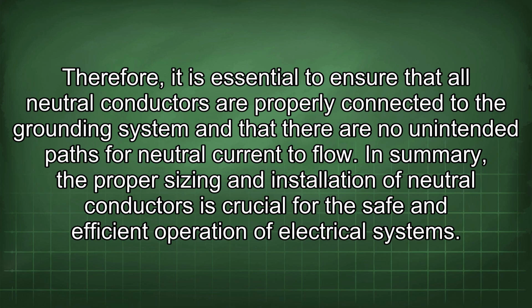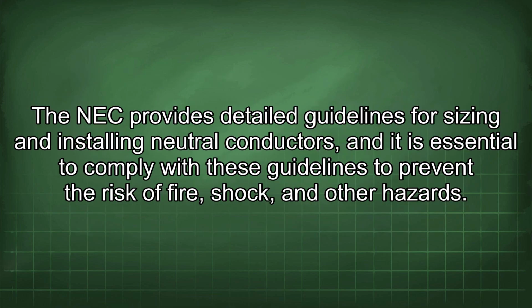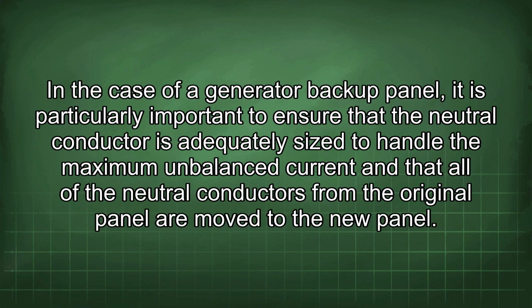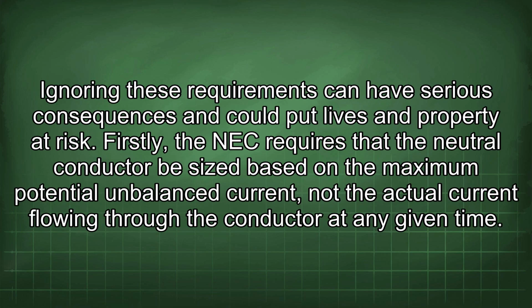In summary, the proper sizing and installation of neutral conductors is crucial for the safe and efficient operation of electrical systems. The NEC provides detailed guidelines for sizing and installing neutral conductors, and it is essential to comply with these guidelines to prevent the risk of fire, shock, and other hazards. In the case of a generator backup panel, it is particularly important to ensure that the neutral conductor is adequately sized to handle the maximum unbalanced current and that all of the neutral conductors from the original panel are moved to the new panel. Ignoring these requirements can have serious consequences and could put lives and property at risk.